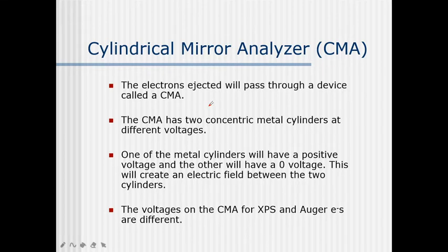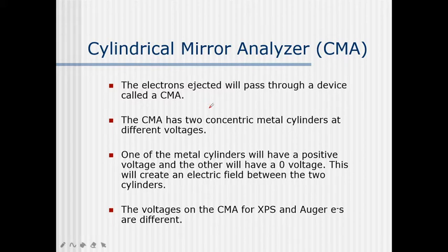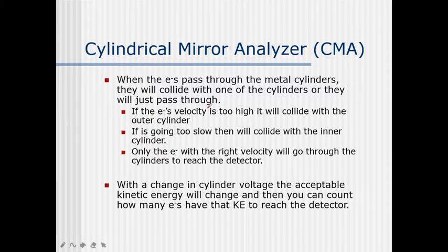One of the metal cylinders has a positive voltage and the other has zero voltage. This creates an electric field between the two cylinders. The voltages on the CMA for XPS and auger electrons are different — for auger electrons, the CMA deals with secondary electrons that are released. When electrons pass through the metal cylinders, they will either collide with one of the cylinders or pass through, which is decided by their velocity.